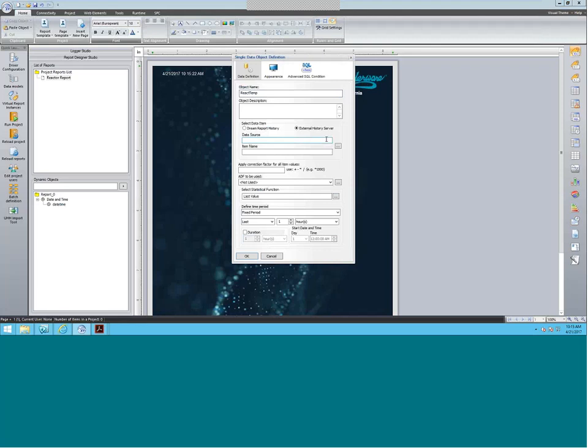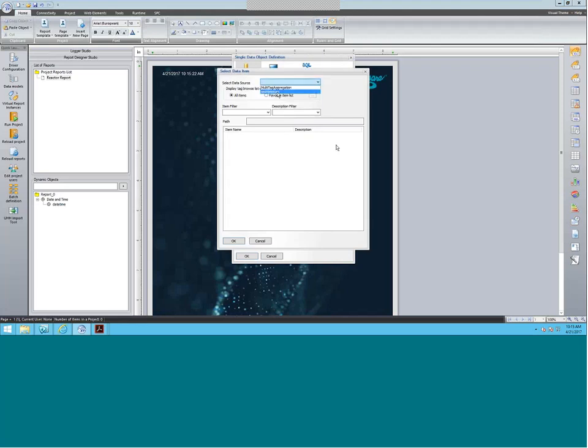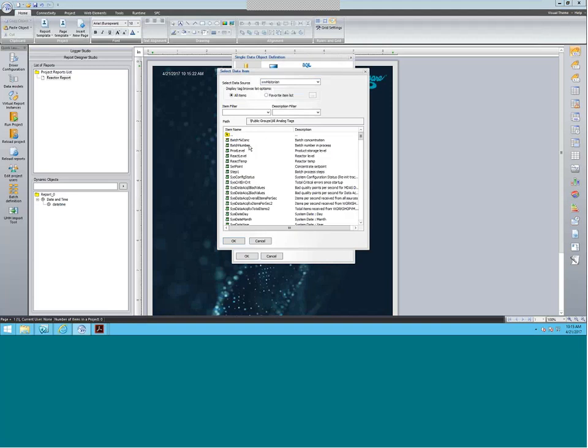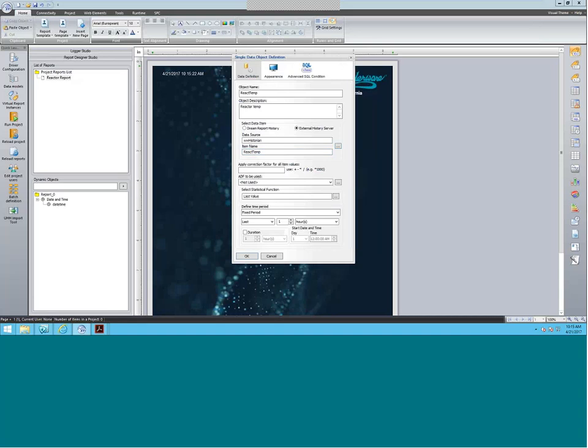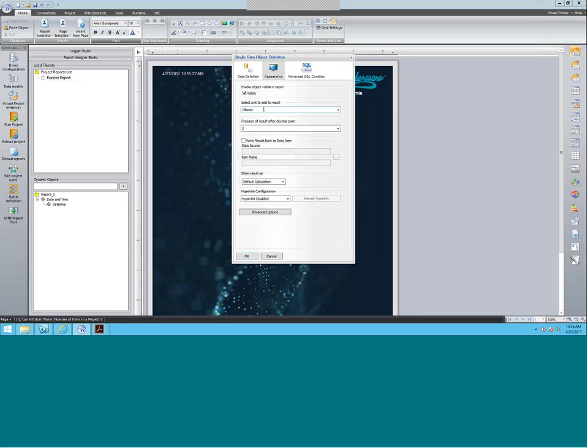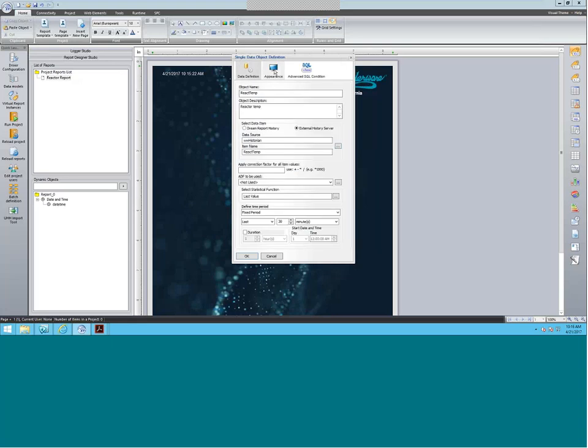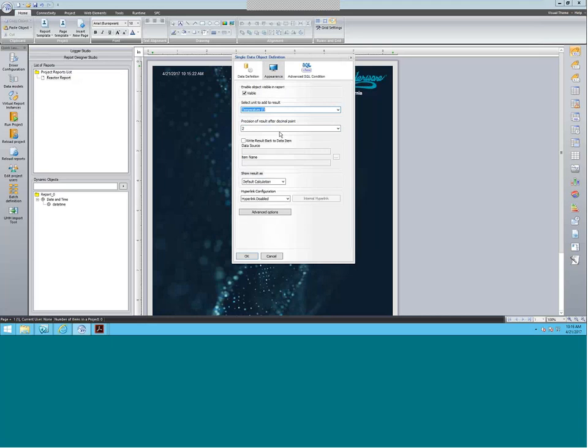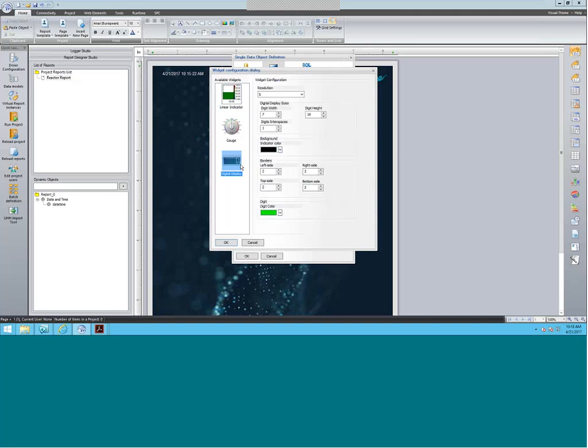We're going to use the external history server today because we put in the historian earlier. Selecting that, you can go to the historian. From here we have a variety of different kinds of tags — analog, discrete, event tags. I'm going to use an analog tag; there's a tag called react temp. You can also type in the item name here in the data source if you know what they are. I'm going to do a fixed period — the last 30 minutes. Appearance is where you put in the values; you can select a unit to add to the result, so here for reactor temp we can select a temperature value. Precision gives you how many decimal points you want. The result is shown as a widget — I'm going to use the digital display, resolution is five, color is green.